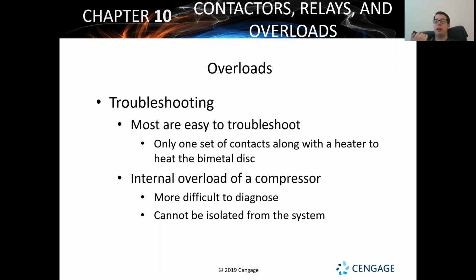I'm going to see, okay, do I have anything for a capacitor that's messing up? Do I have one that's kind of low? I'm going to check my windings on everything. I'm going to check my amp draw on everything and make sure that it's not too high or too low. I'm going to check the resistance of my coils to make sure that I don't have an open or a short or excessive resistance for any reason. And then, that's when I'm really looking into all of my different components on the system, beyond just the overload and what it's protecting, but also everything else that it is in series with, what it's functioning alongside with. That's what we have to look at.